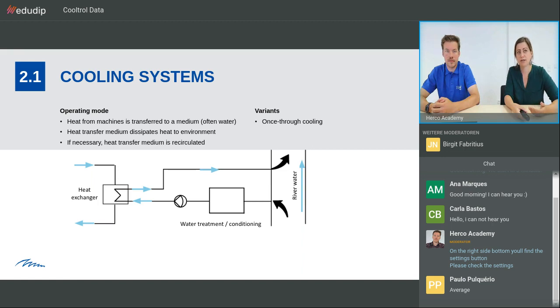This is the simplest method because actually there is no recirculation, so it's not a cooling circuit really, it just goes once through as the name says. It's simple in terms of handling. There is, apart from water treatment, very little machinery really. On the other hand, there is a very large water use. As you can imagine, if you just use the water once, the water use is in some cases enormous. It has also been a problem about the heat load that goes to the rivers. In the last years, this thermal pollution of rivers has been an increasing topic, and that's why this system has sometimes been replaced by circuits. It's still a method of choice for, let's say, very large factories that are next to a river, especially power plants, but very often it is at least combined with a cooling tower downstream of the heat exchanger.